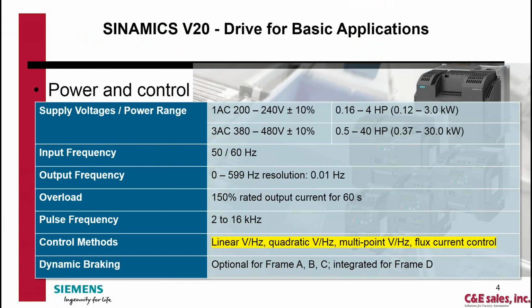It comes in these flavors, kind of the voltages: single phase, 200 to 240 volt, fractional horsepower to 4 horsepower, and then 3-phase, 380 to 480 volt, half up to 40 horsepower. Again, you see highlighted there, it is for linear volts hertz, quadratic volts hertz, but all tied back to just volts hertz mode. Flux current control gives you a little better control, but still no real torque control.